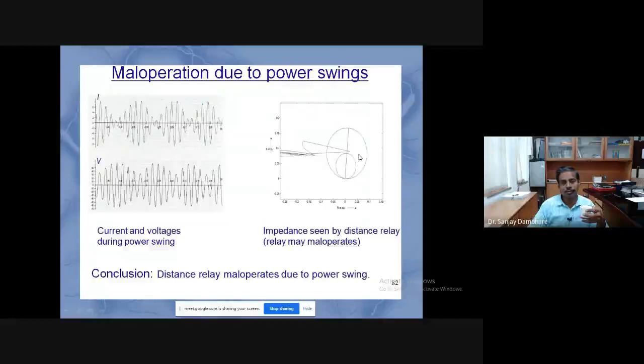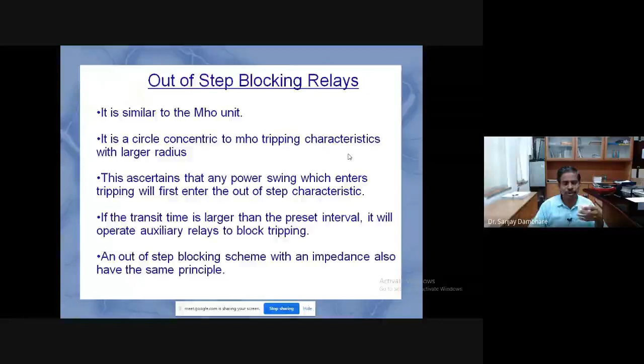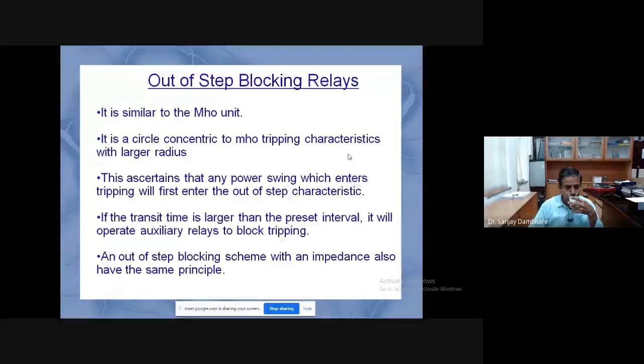From these currents and voltages during the power swing, we can very well see that the relay will trip on the power swing. So there is some intelligence to be provided to the distance relay so that it can block against the power swing, and that is how the power swing block is set up.